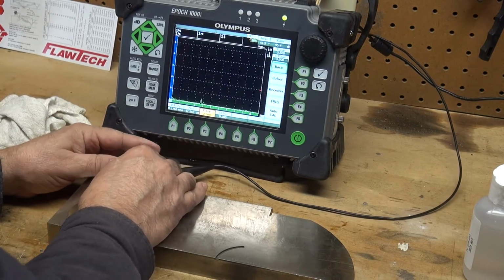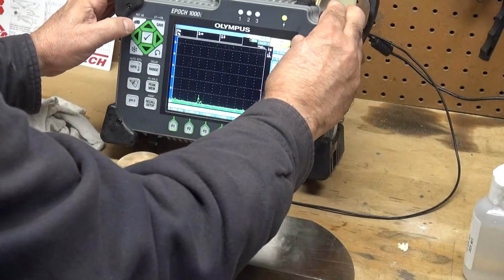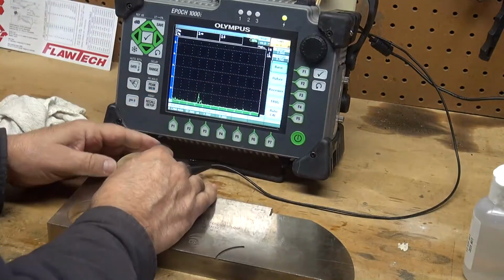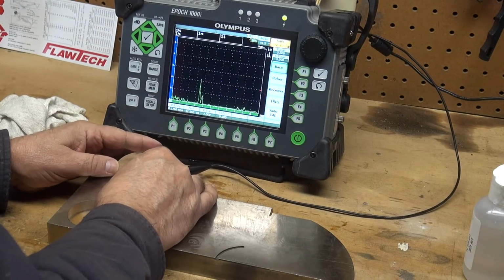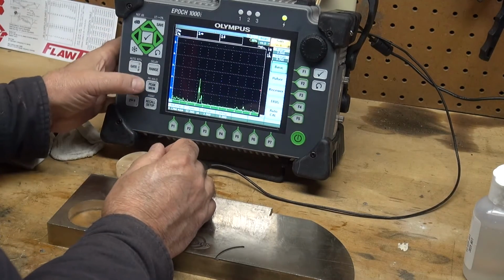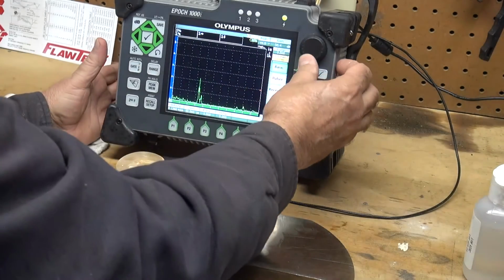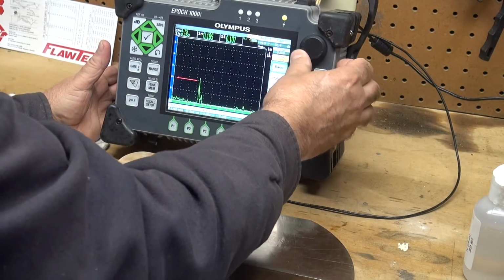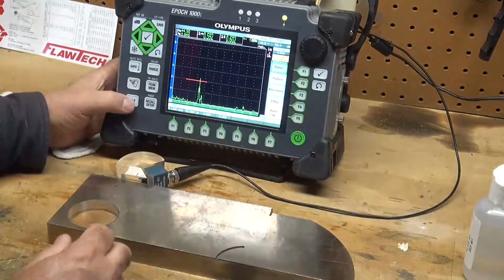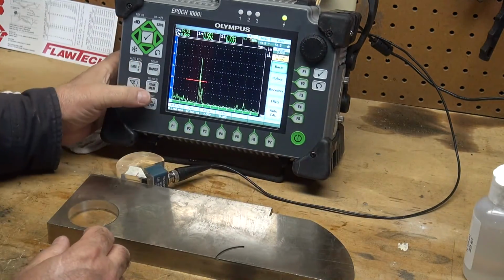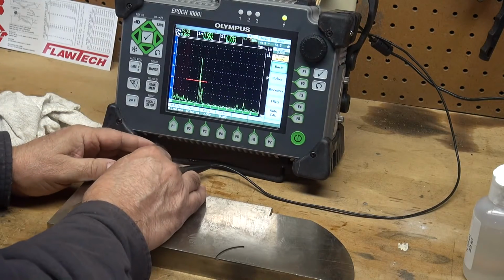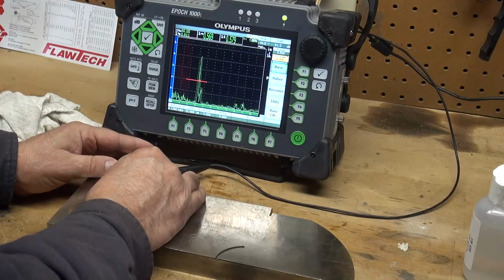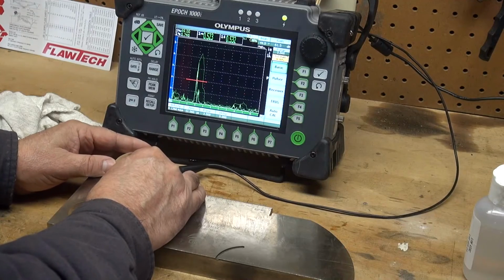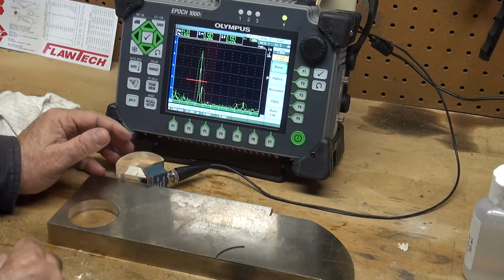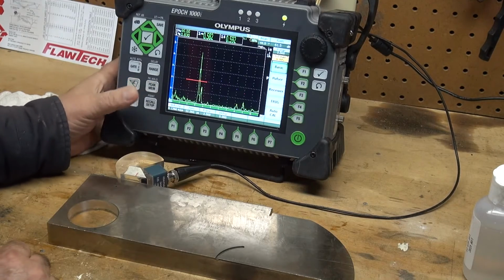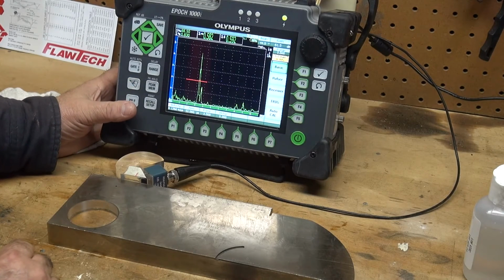I can put a little bit more gain in here. I can see this signal. There's that hole, that side drilled hole. Let me take my gate and bring it over to capture that. Oops. There we are. Let me take that to auto 80. And let's look at the peak memory. I want to peak this out. Again, that's a reflector from the side drilled hole, 0.6 inches deep. And there it is. That's my reference point.